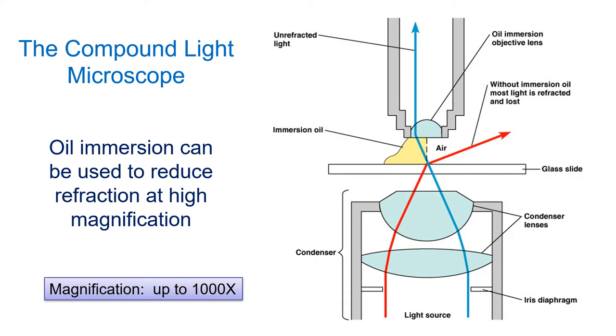When using a high-power objective — the 100x objective, for instance — we use a droplet of immersion oil between the glass slide and the objective lens to ensure we collect as much light as possible. Without immersion oil on the highest magnification objectives, we get a very dim image because we're losing a lot of light to refraction, and we also get poor resolution.